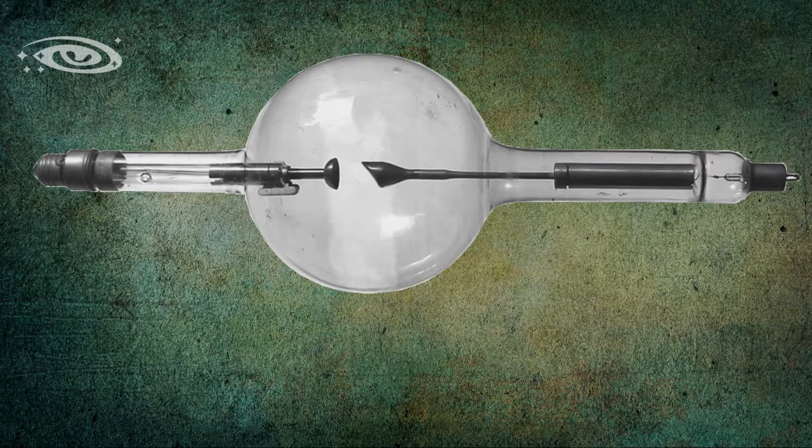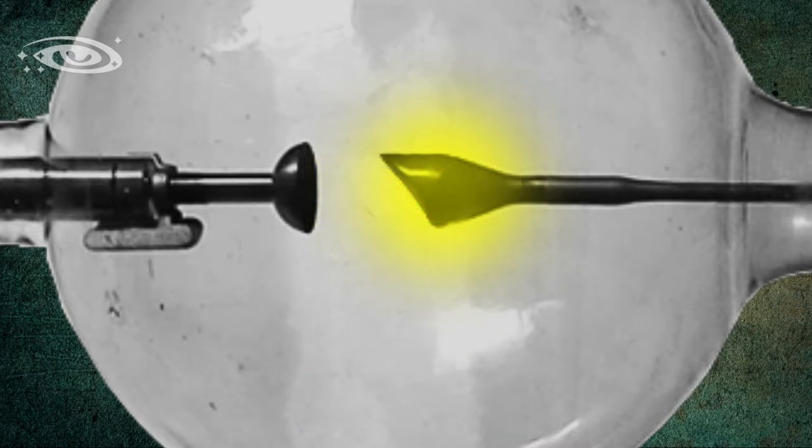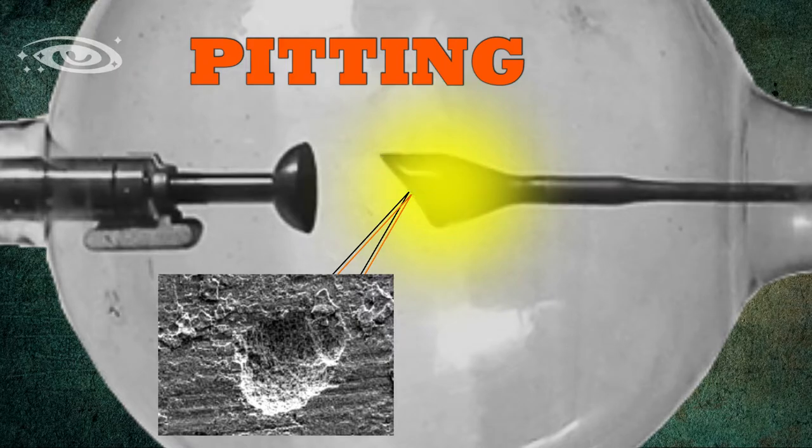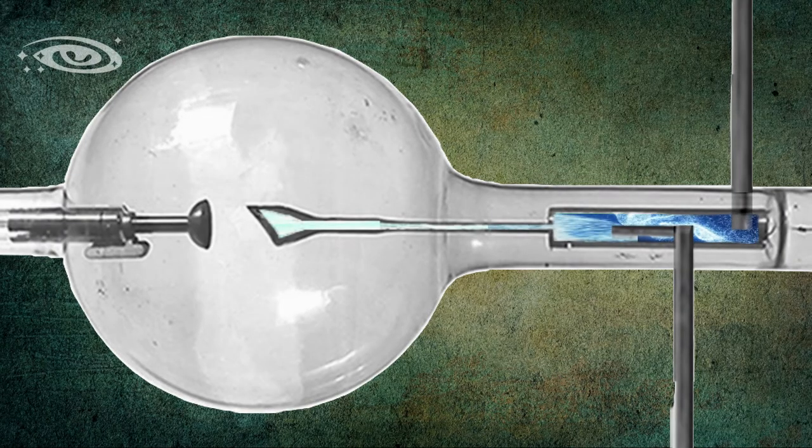Due to interaction of these high velocity electrons with the target of the anode, there will be production of an enormous amount of heat. This heat may damage the target so that tube life is going to be reduced. If the heat is not quickly dissipated from the target, target may get soon pitting. Pitting means hole or crack is created on the target. If pitting happens, X-ray intensity is going to be reduced. So to dissipate this heat properly, they supplied water behind this anode.